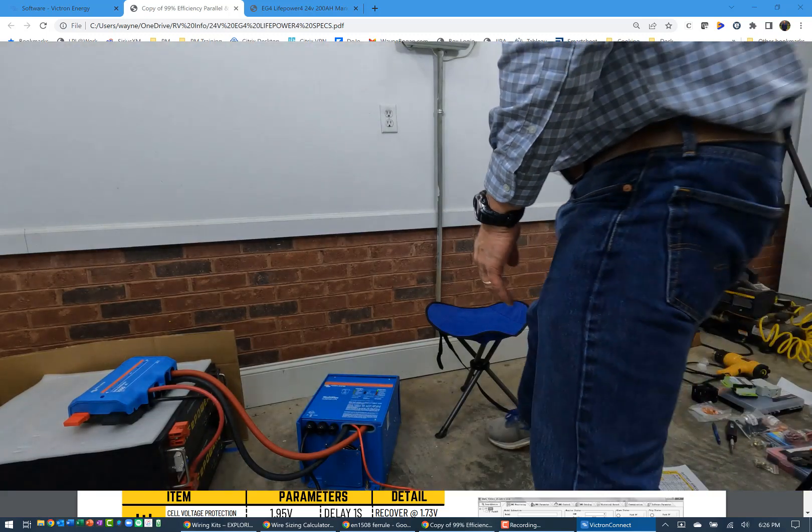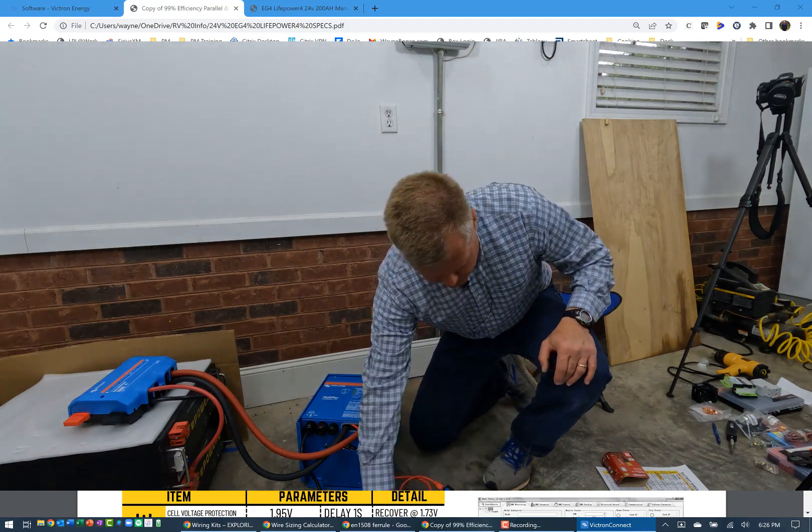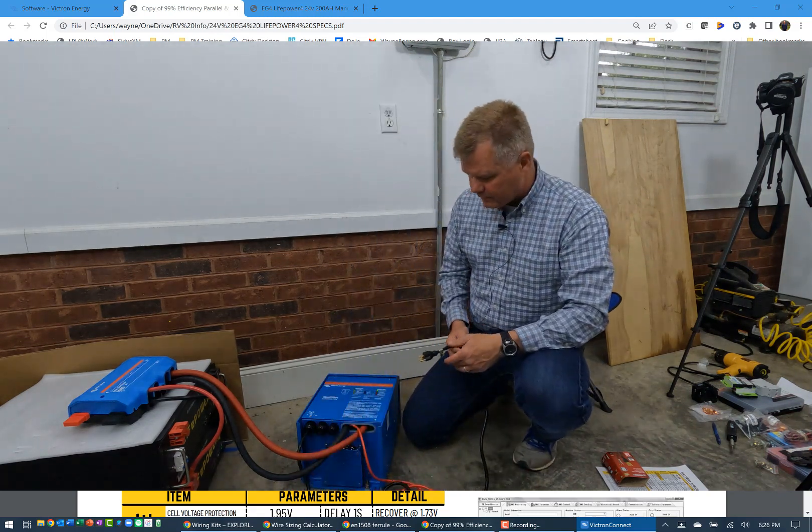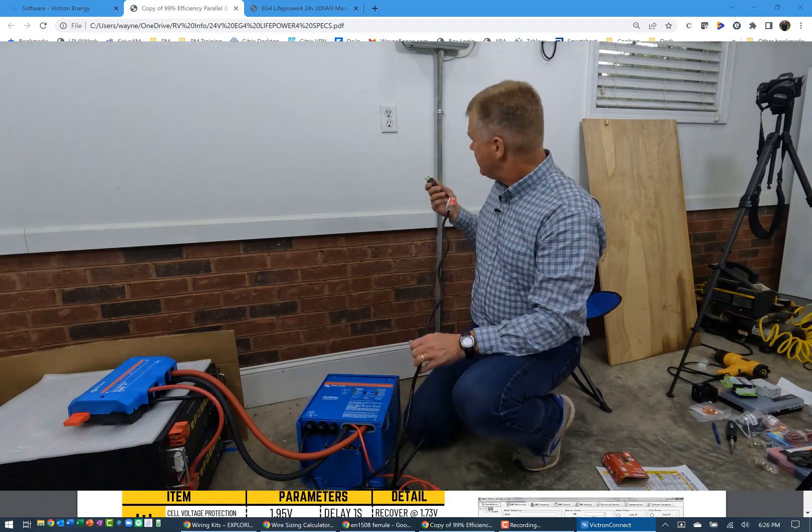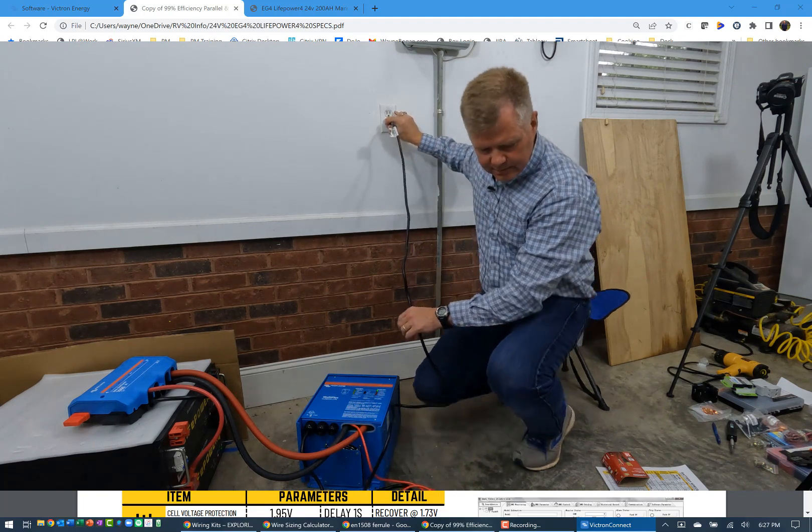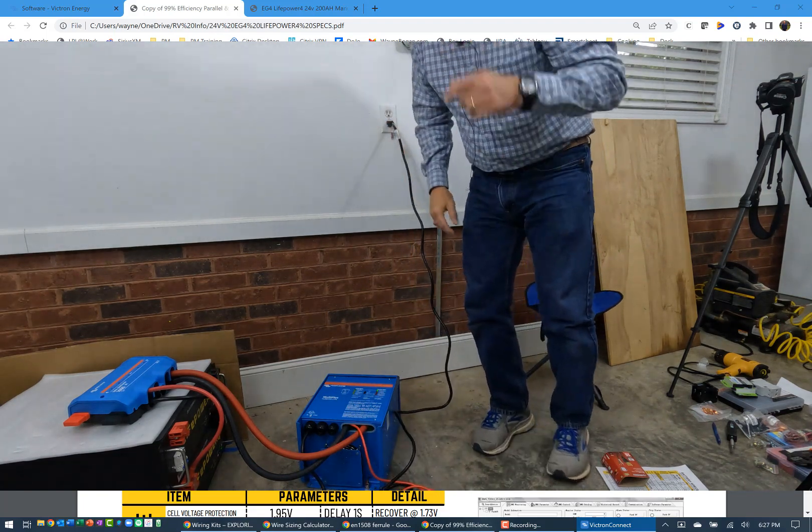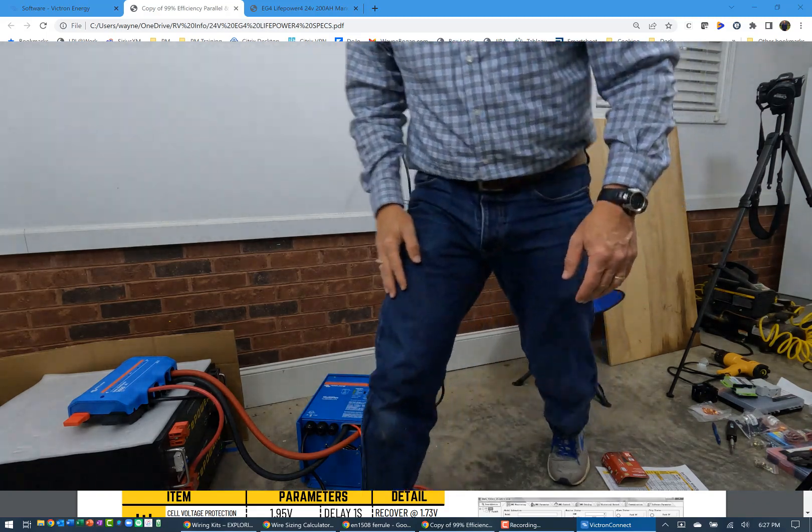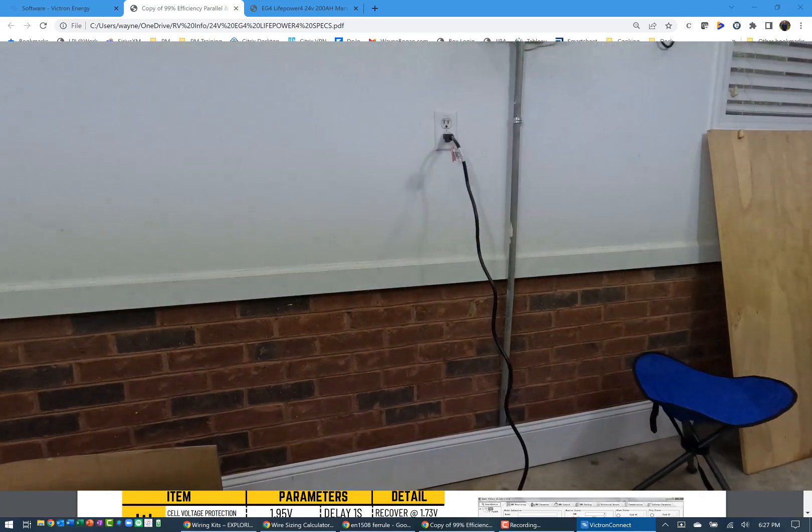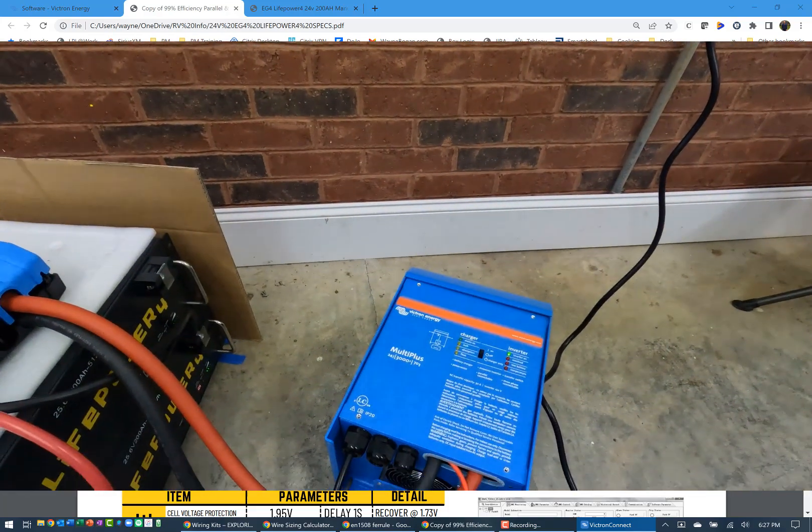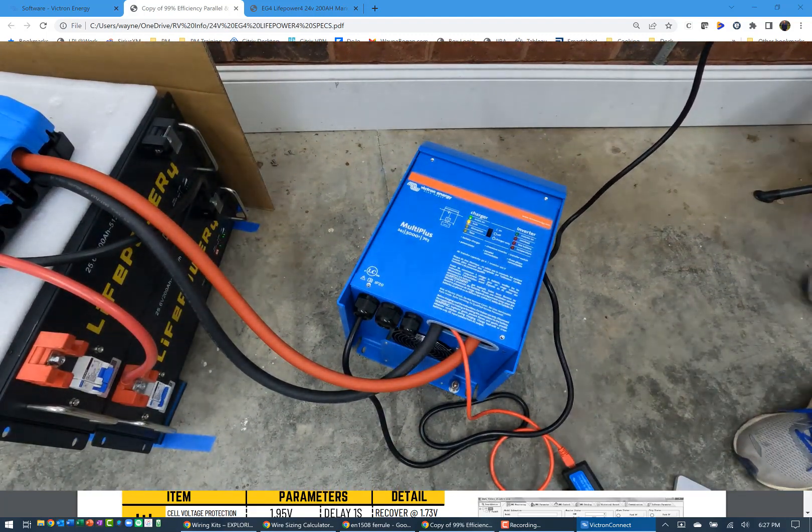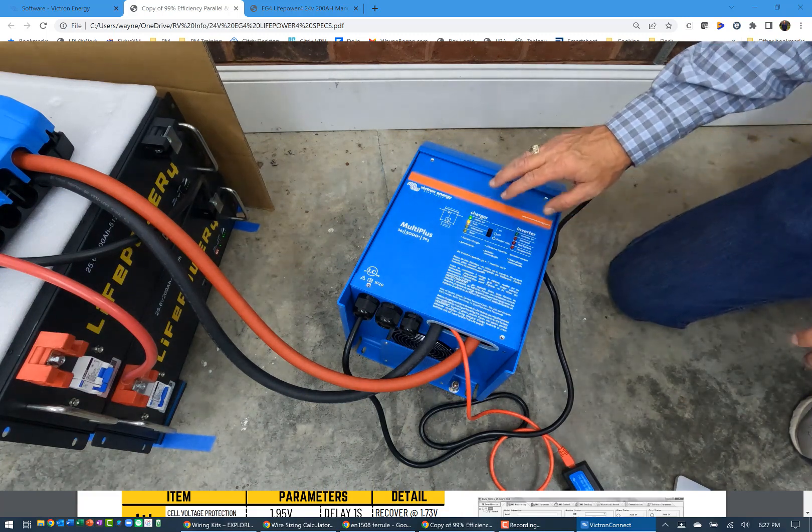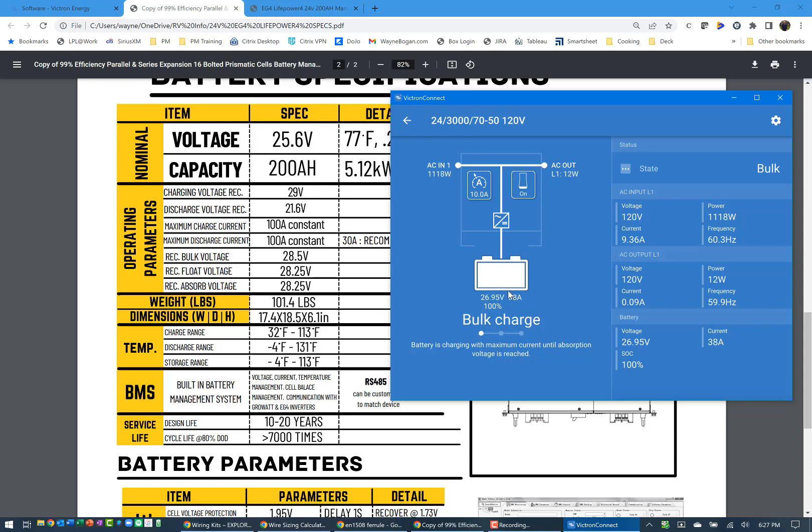Okay, so we're using the software to look at and watch to see what happens on the inverter. I have a GoPro set so that you can come in and see. We're going to simply plug in the outlet. You'll see in the software the change that takes place. I'll move the camera so that you can see closer to what happens on the inverter. You can see the inverter switched, and on the GoPro you can see that it came in the main, and it's now doing a bulk absorb. And the software, you can see that I now have AC in 1100 watts that are coming in and charging the battery. Right? So, we can see that it's going through and doing the charge, and we'll let it run as it goes through and gets the battery up to speed.